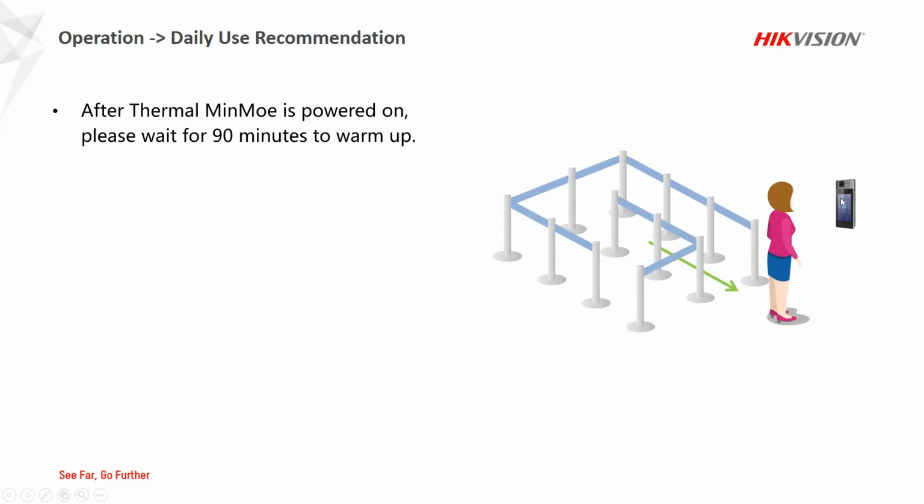Then for the daily use recommendation, I'm giving you some tips here. Because the Thermal MinMoe has the thermal camera on top, we would always recommend to wait for 90 minutes to make sure the product is warmed up to ensure accurate temperature reading.